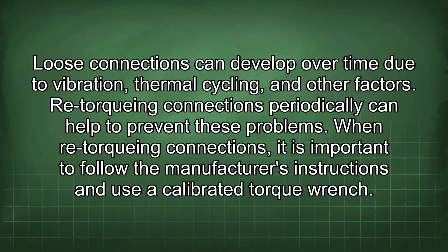When retorquing connections, it is important to follow the manufacturer's instructions and use a calibrated torque wrench. Also, inspect the connections for signs of corrosion or damage. Replace any damaged components and clean corroded connections before retorquing.